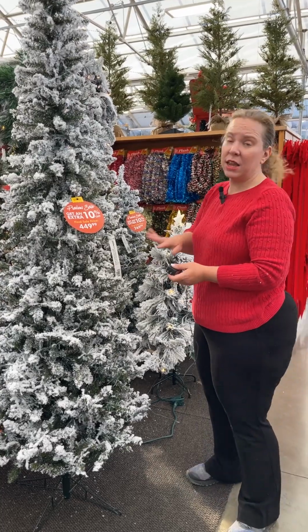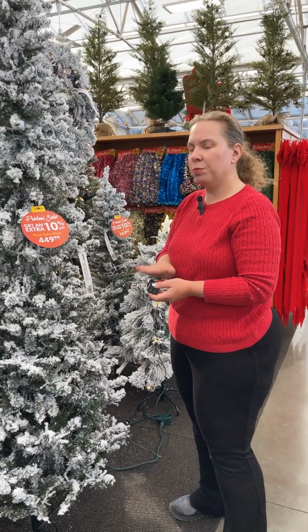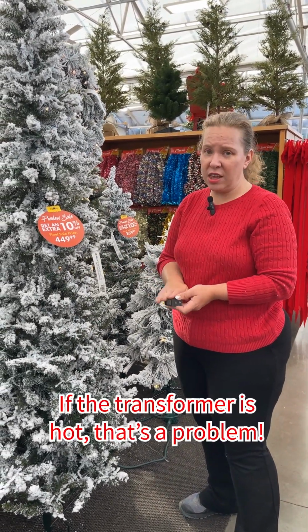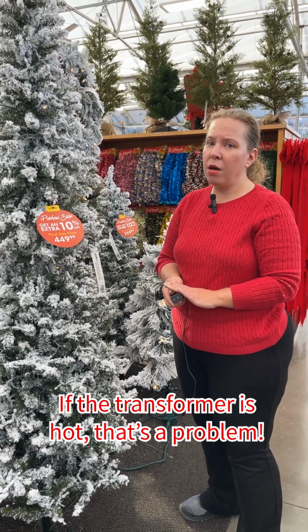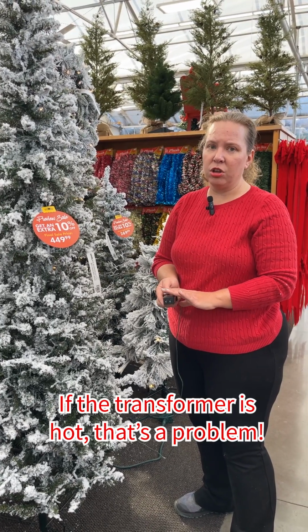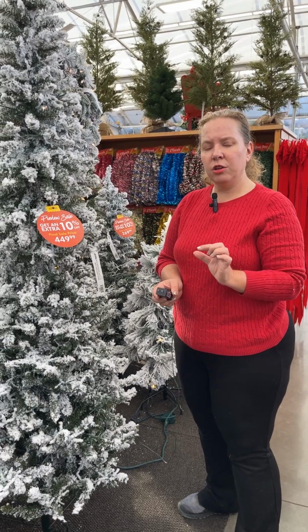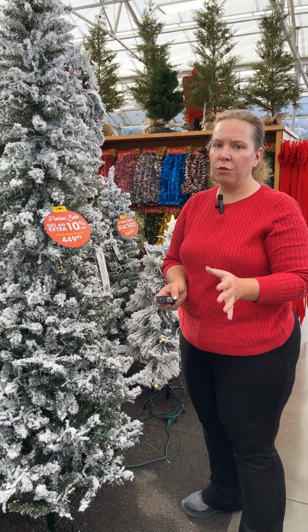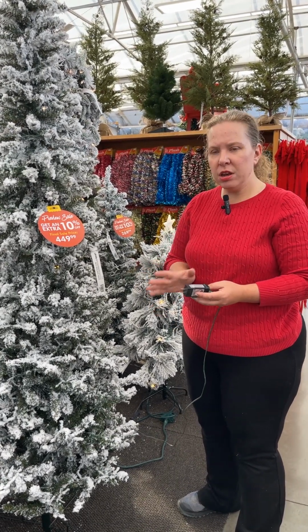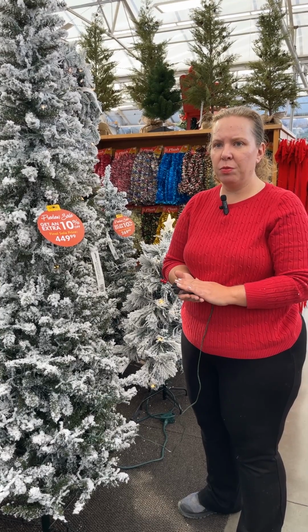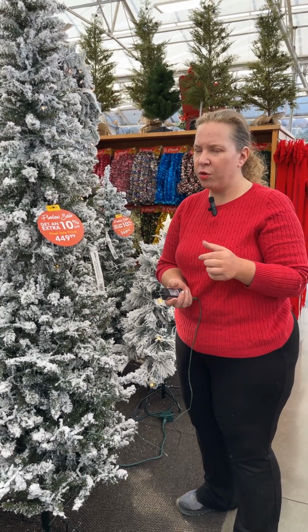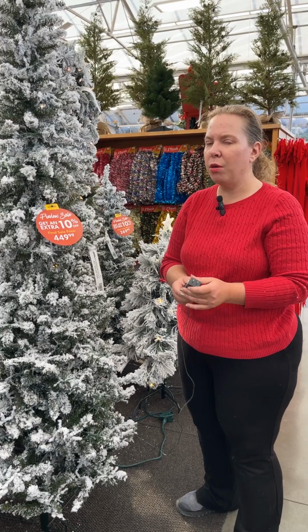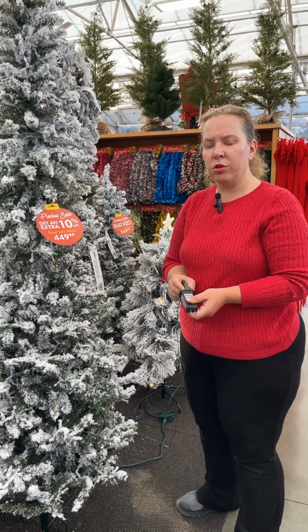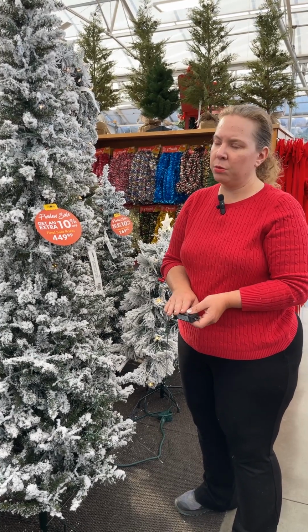If you go up to any electrical system and touch the plug-in and it's hot, there's heat coming off of it, there's probably a problem with that electrical connection. Generally speaking, electrical plugs should be running at roughly room temperature—70 to 90 degrees is typical. If you touch something and it's hot to the touch, over 100 or 110 degrees, there's probably a problem with that electrical connection. You never want heat when it comes to electrical.